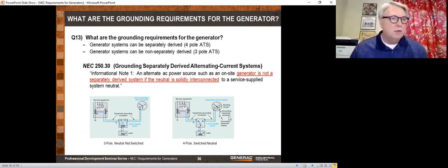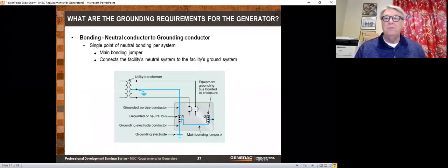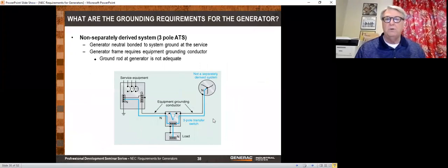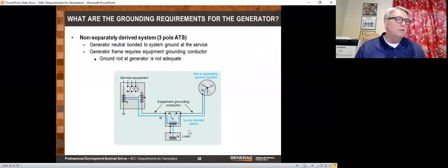This is very confusing, and a lot of times contractors are just not going to know this. If you put a neutral to ground bond in and you have a 3-pole switch, you have violated the code. And if you don't put the neutral to ground bond in and you have a 4-pole switch, you've also violated the code and you've caused some problems. Now, this shows the neutral to ground conductor right there. It's just basically a wire that connects your neutral to ground. You can only have one on any given system. Of course, if you go through a transformer, you're going to have another one, but on any system, you're just going to have the one and only one. You must have one. You cannot have more than one.